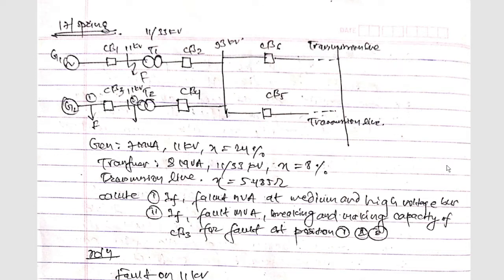Hello and welcome to my channel. Today I am back with another important numerical on power plant designs. Here you can see a single line diagram. The generator is rated 7 MVA, 11 kV with x = 24%. The transformer is rated 8 MVA, 11/33 kV with x = 8%. The transmission line x = 5.485 ohm. We need to calculate fault MVA at medium and high voltage bus, and the fault MVA breaking and making capacity of circuit breakers for fault at positions one and two.